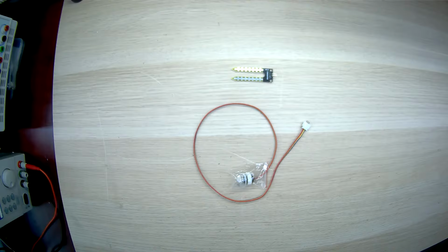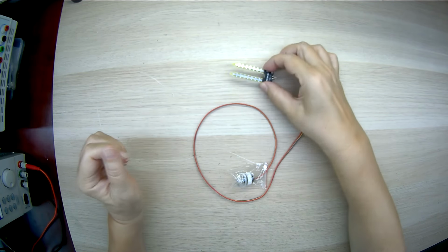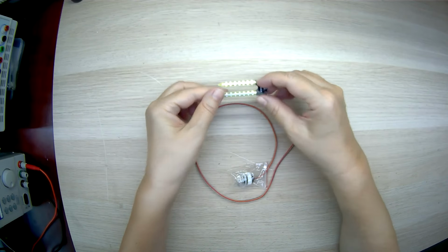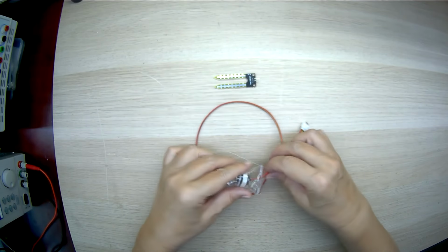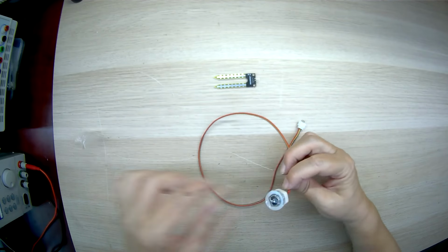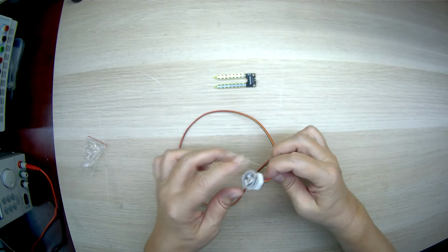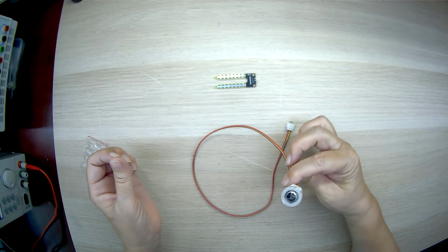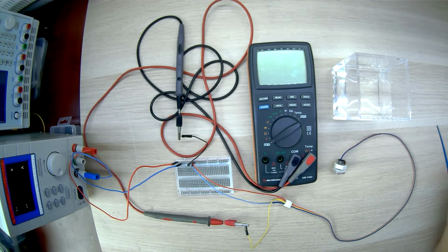There are various types of water presence sensors available. You can use simple two-conductor probes, but we have a better solution in our hands, an optical water sensor. We will use this particular sensor. It functions by detecting changes in the reflection coefficient between different mediums, water and air. Let's conduct a sensor test.